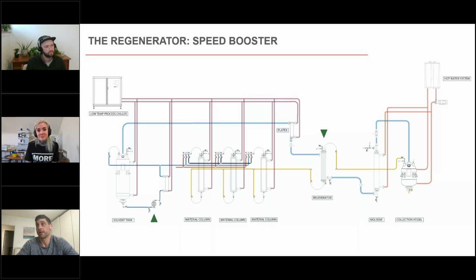A lot of people here have either the ETS, MEP, MEP Mini, or the bigger MEP 30. We've done a number of projects upgrading the MEP 30s. Lyndon, can you talk to us about the throughputs once you tweak that system to do full passive recovery? Once you get a plate exchanger on there, you typically go from about one pound a minute up towards two and a half pretty quickly with some passive recovery upgrades. We always shoot for 5 pounds a minute to try to 5x the system.